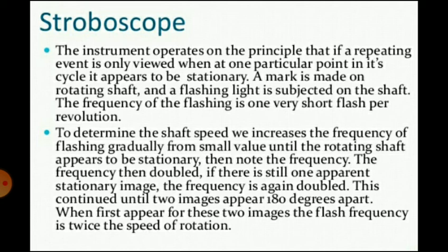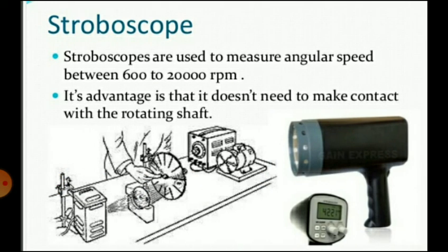The stroboscope consists of a source of flashing light whose frequency can be varied and controlled. This source is called a strobotron. It is a hot cathode gaseous discharge tube. It has a cathode, an anode, and two grids. One is called the inner grid and the other the outer grid. The tube has a maximum flashing rate of 300 per second with an effective discharge time of 10 to 100 microseconds. The discharge current may be as high as 300 ampere.